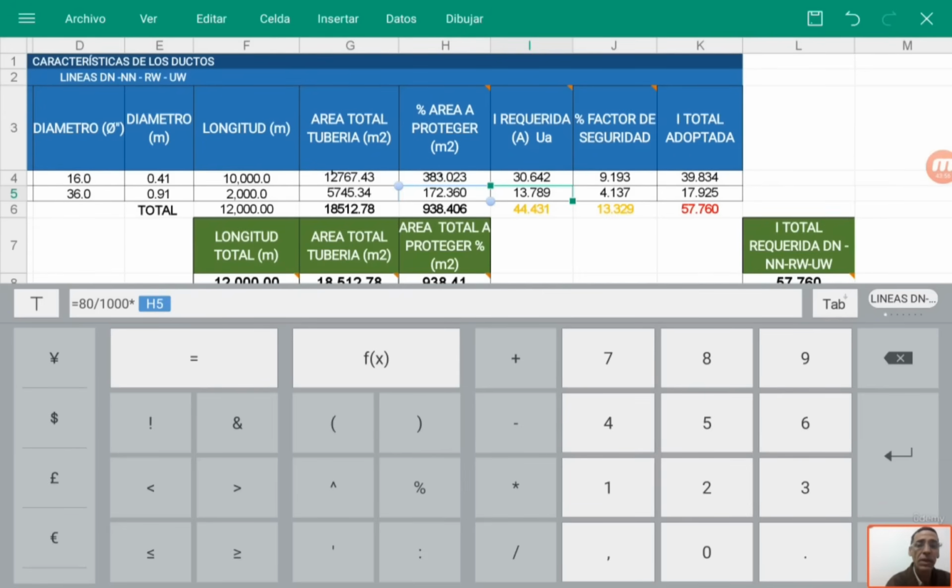So, the safety factor. Let's see what it is here. The safety factor here is 30%. Sometimes the client might say, no, that's too high, set it to 20. Well, that's fine, you can lower it to 20, but don't go below 10. The safety factor is always something for you. It's a cushion.